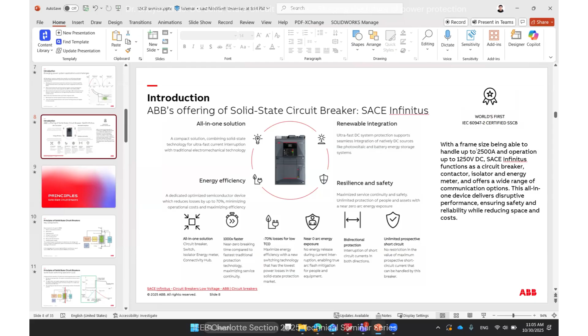For some applications, if we need more intelligent protection, we need solid state circuit breakers - for more comprehensive or more intelligent protection, like faster response, for example for DC. A fuse might be as slow as millisecond response speed, and for DC that may not be safe anymore. Especially for DC, if we have these solid state breakers, the remote resettability is very important in many cases. Okay, thank you.